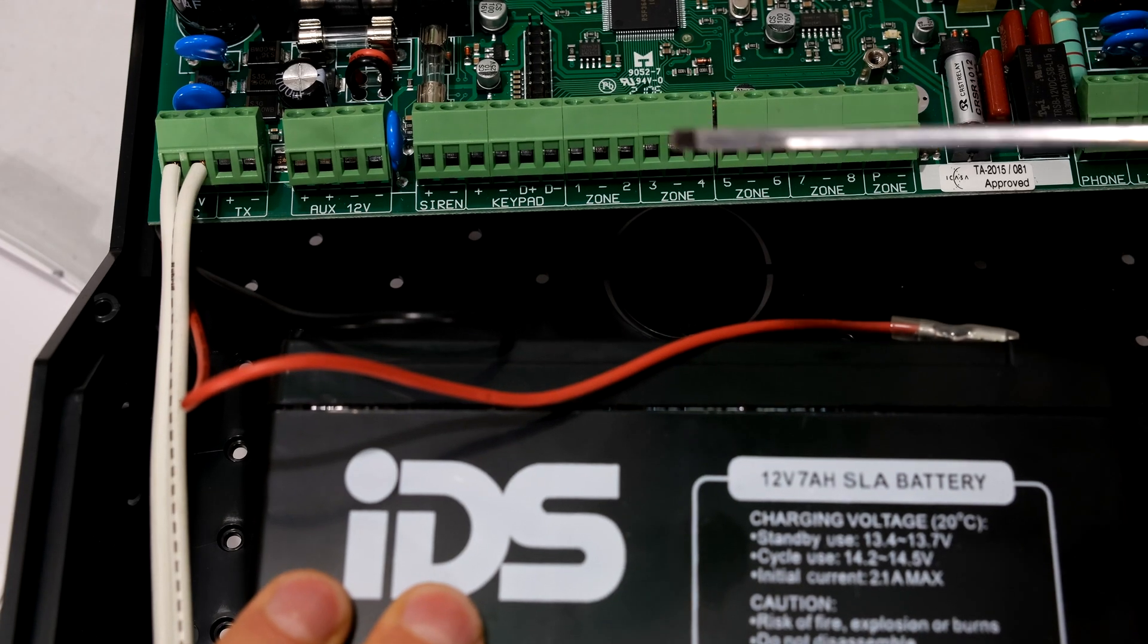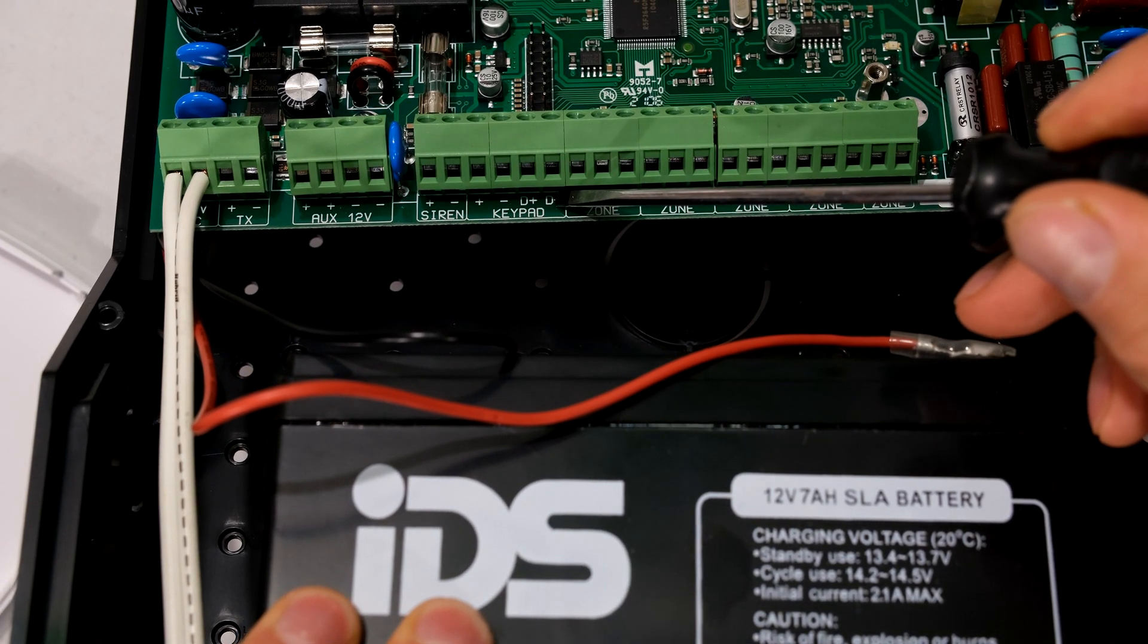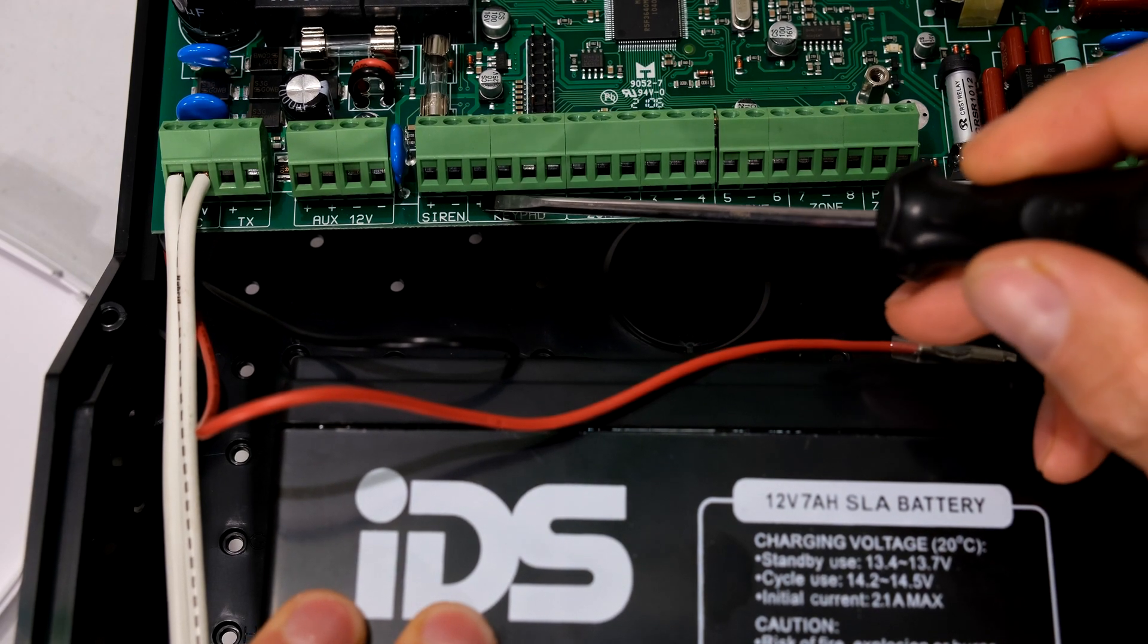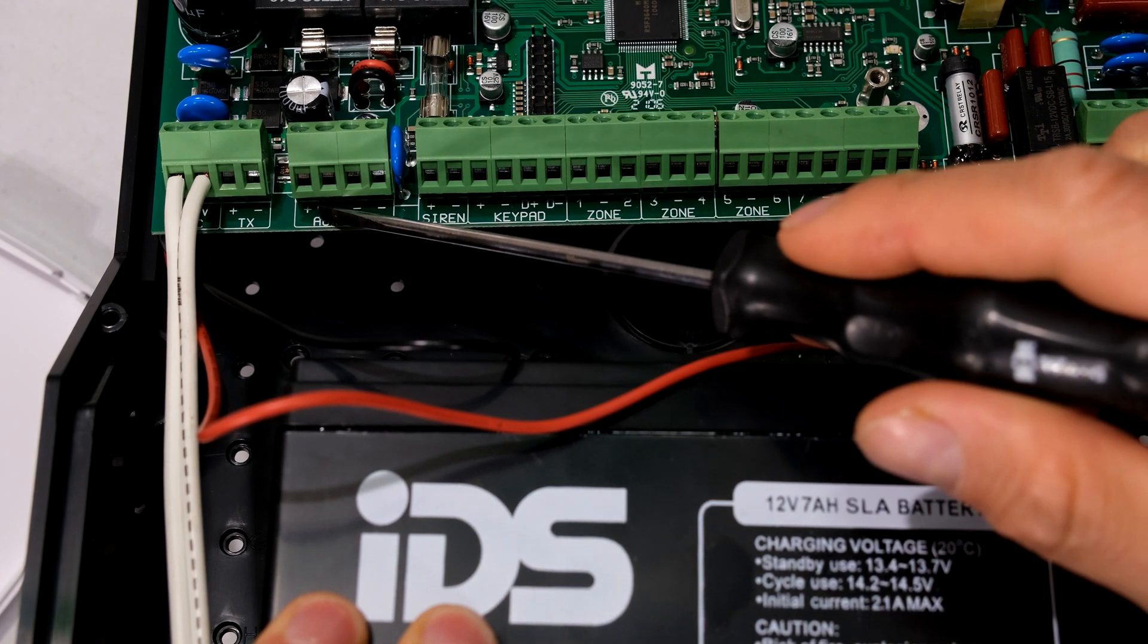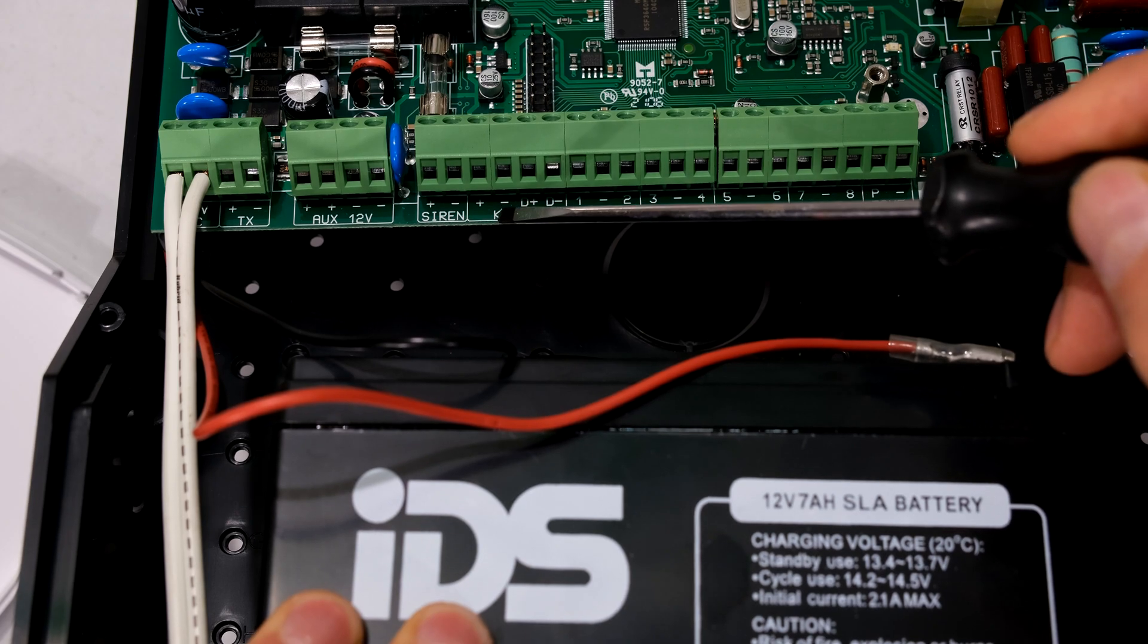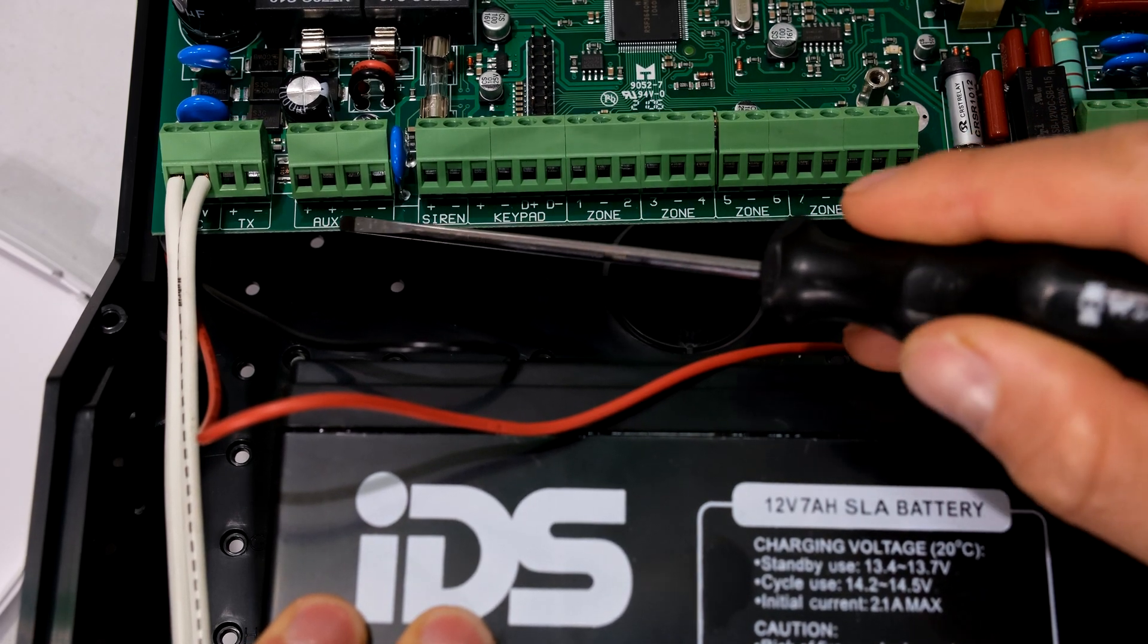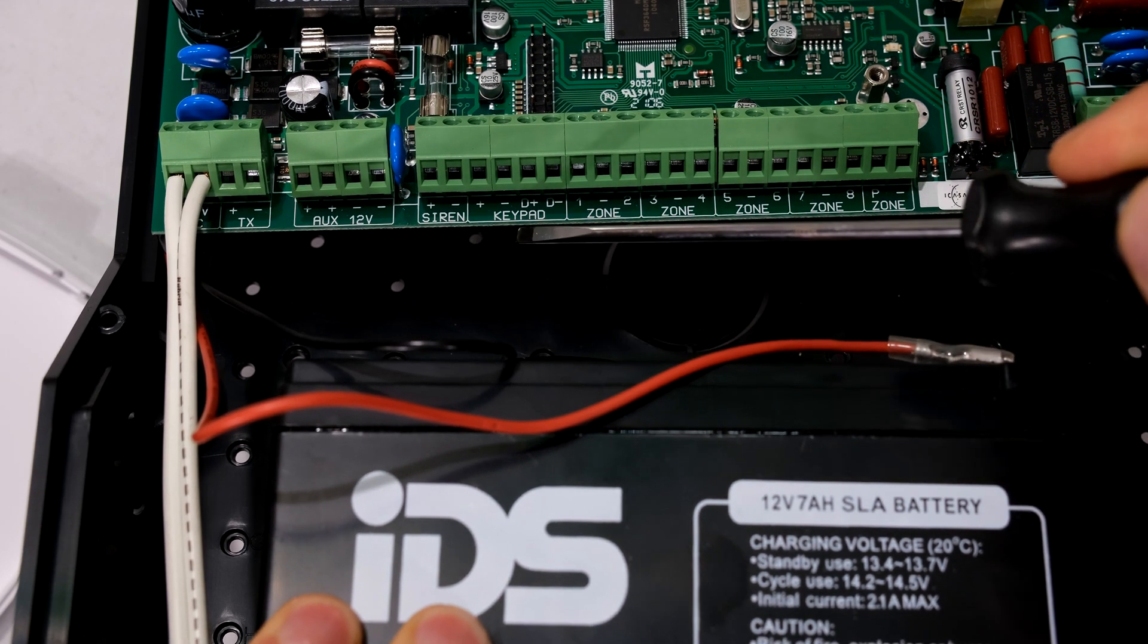Now in order to connect the keypad to the panel, we need to use the D minus over here, the D plus over here, and then the positive and negative. This positive and negative over here is actually the same as this positive and this negative over here. It's just giving you the option of connecting directly over here. If you run out of space, you can use the positive and negative over there. It's the same rail.